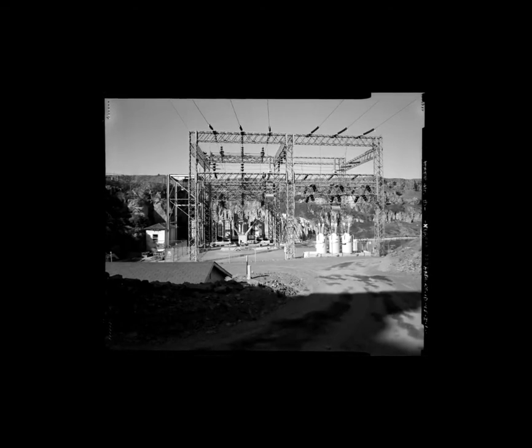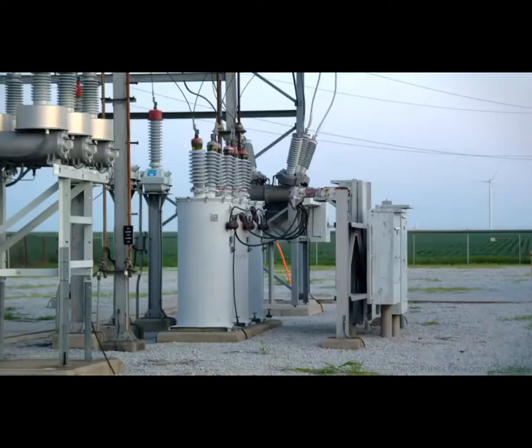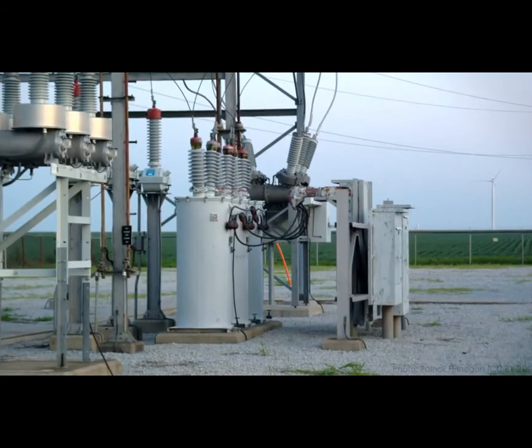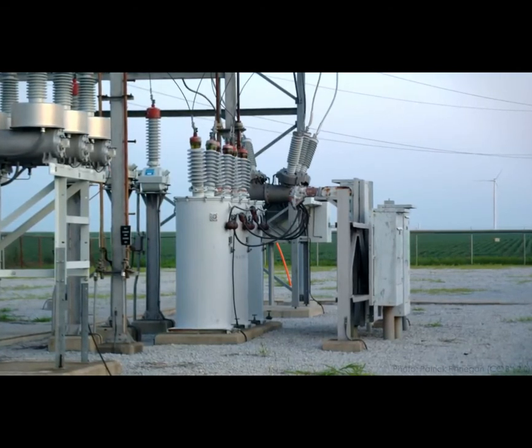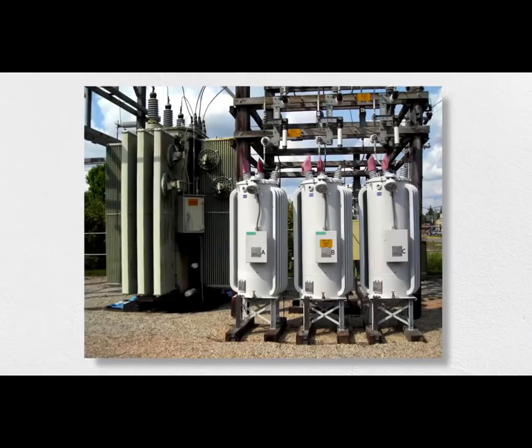The simplicity of transformers also means it can be difficult to make fine adjustments to the power leaving the substation. Because of this, many substations include equipment for monitoring and controlling the power on the grid. Instrument transformers are small transformers used to measure voltage or current or provide power to system monitoring devices. Regulators are devices with multiple taps that can make small adjustments up or down to the distribution voltage on feeder lines leaving the substation toward customers. If you look closely, you can sometimes see the regulator dial indicating the tap position.